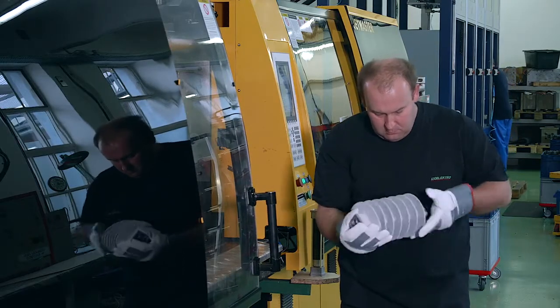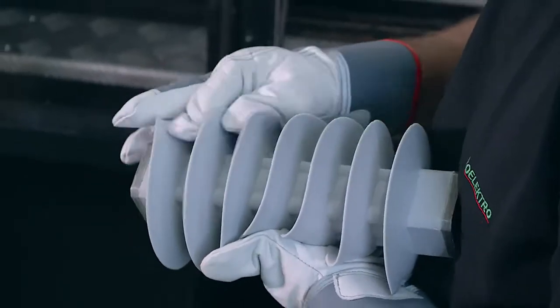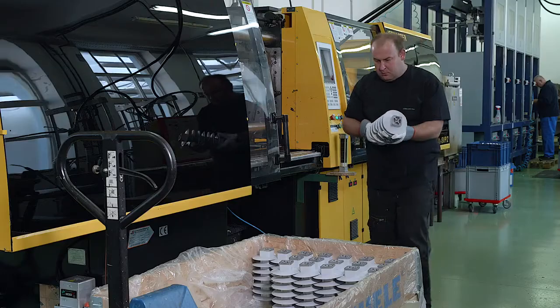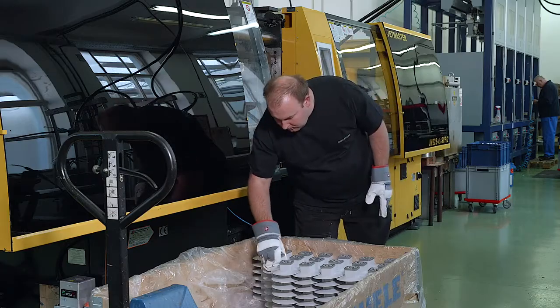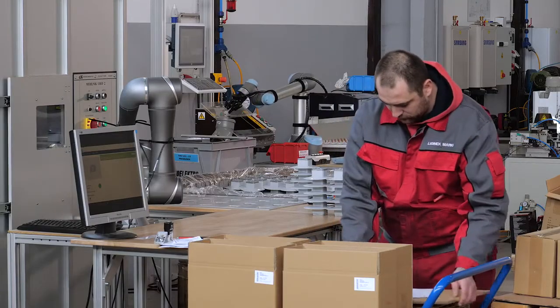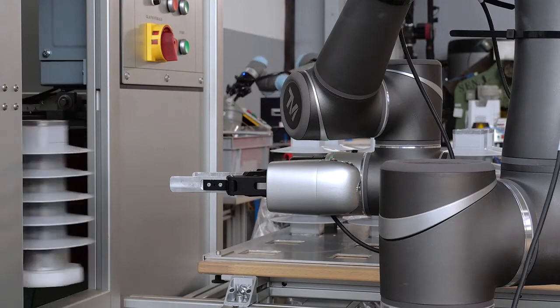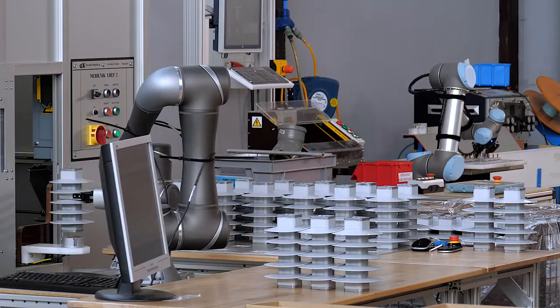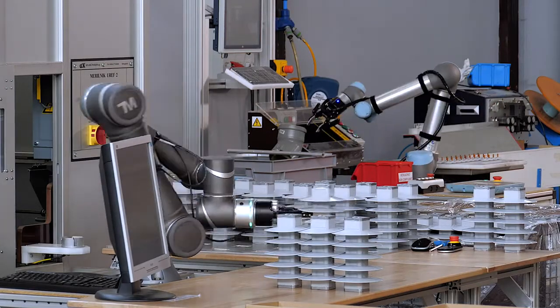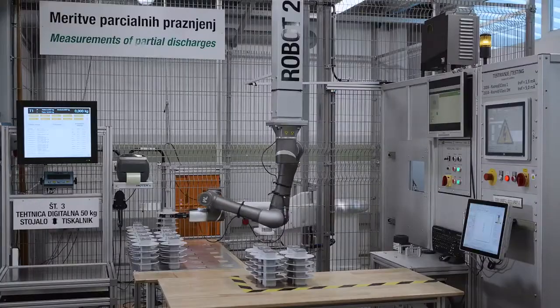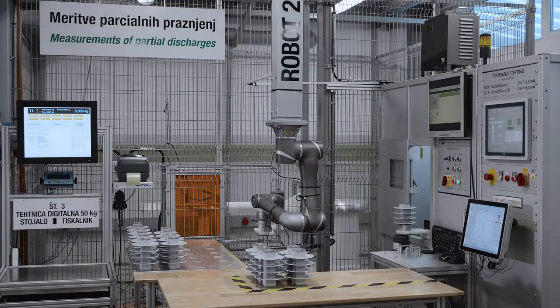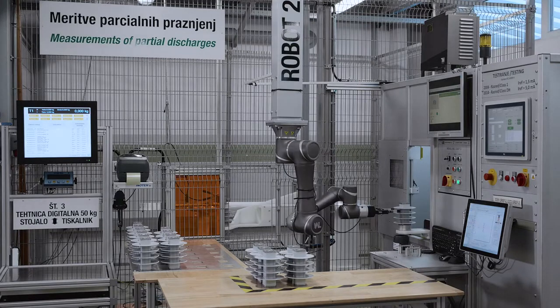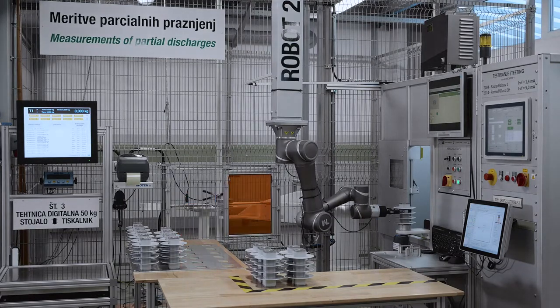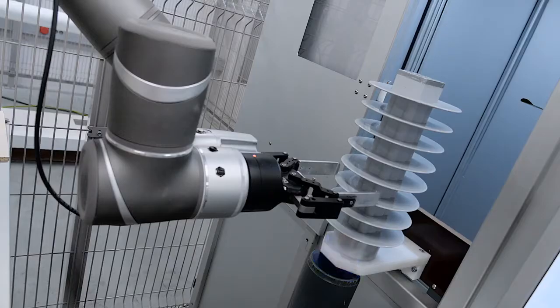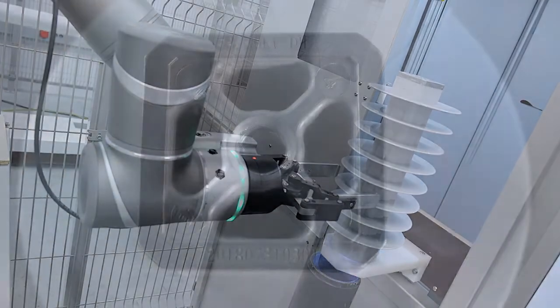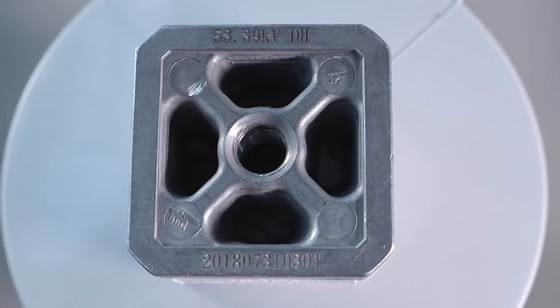After siliconizing, we do a visual check of the silicone coat and a mechanical test of silicone adhesion to the surge arrestor core. The final quality control involves measuring the partial discharge and reference voltage. This is done with the aid of a robot. After the measurements are complete, the surge arrestor is engraved along with the value of the residual voltage with a unique number, which represents the date on which the test was performed and the serial number of the measurement.